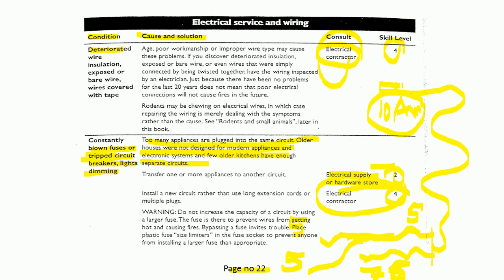So sometimes what I do, I don't know how the system works. I say, okay, you know what? Let me replace this one with a 20 amp. It looks easy. I will turn the electricity off, and replace the 10 amp with a 20. It will never go down. But what's the problem? Now 10, 11, 12, it will be 17 ampere. It will go all the way here, and this wire will be overheated, and maybe it will melt, and it will be the source of a fire. Many times the reason for the fire is an electrical short circuit or overloading, such things, it may be a disaster for that house or the building.